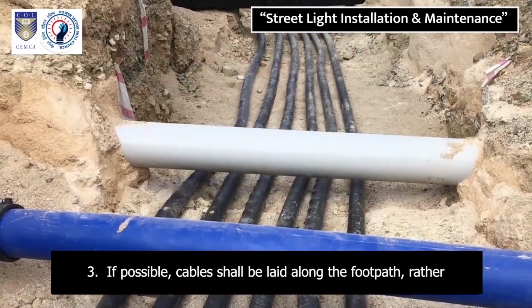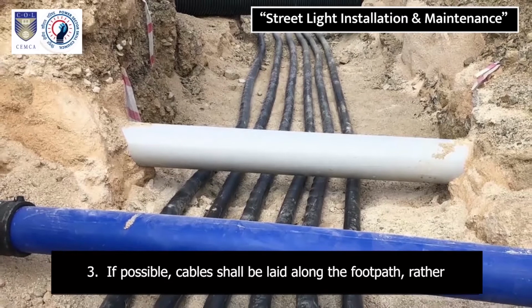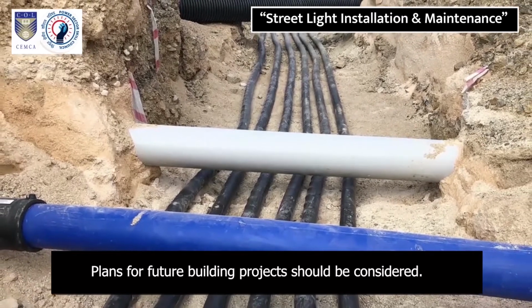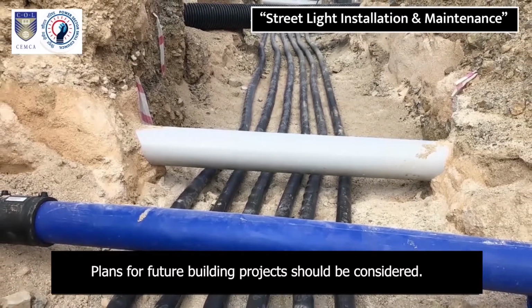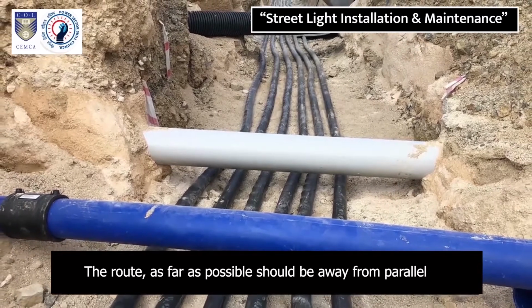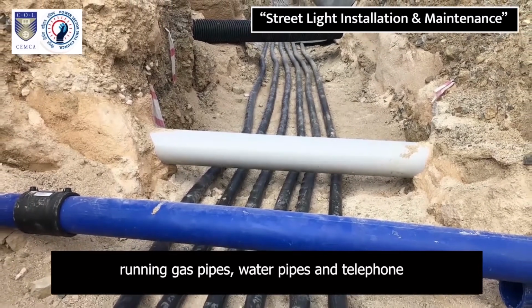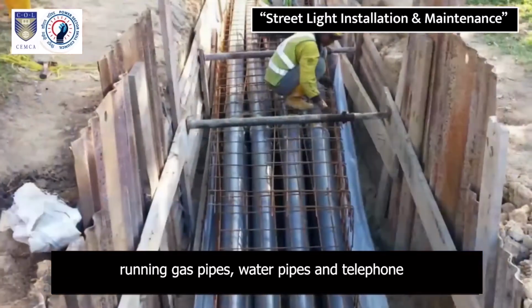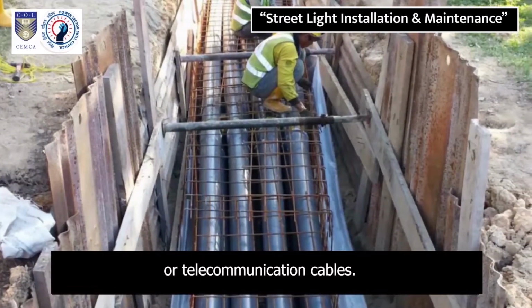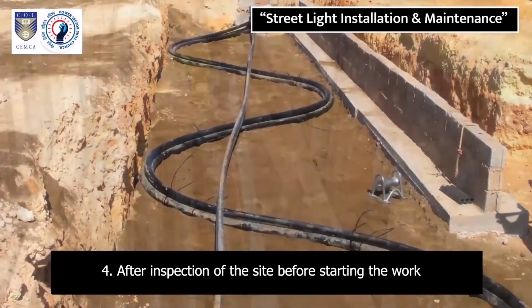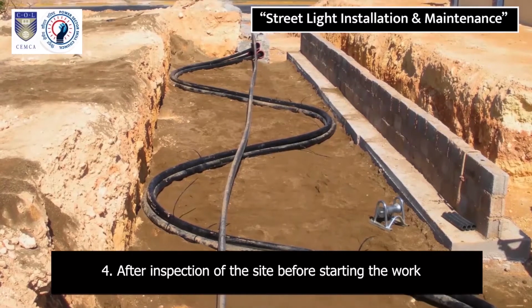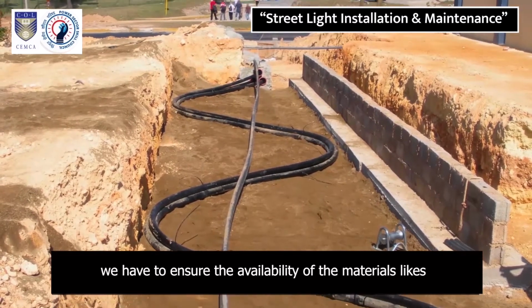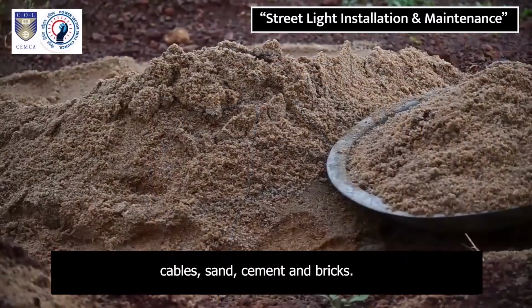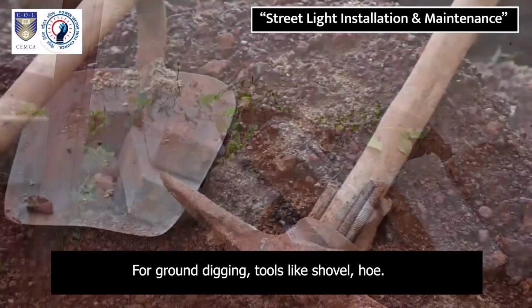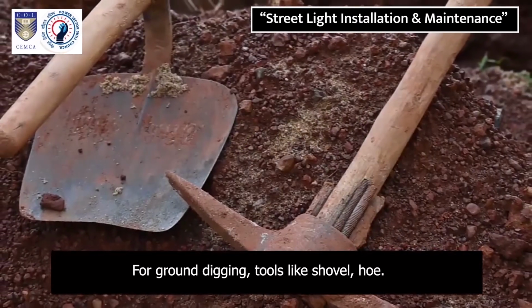3. If possible, cables shall be laid along the footpath rather than the carriageway. Plans for future building projects should be considered. The route, as far as possible, should be away from parallel running gas pipes, water pipes, and telephone or telecommunication cables. 4. After inspection of the site before starting the work, we have to ensure the availability of the materials like cables, sand, cement, and bricks. For ground digging, tools like shovel, hoe.